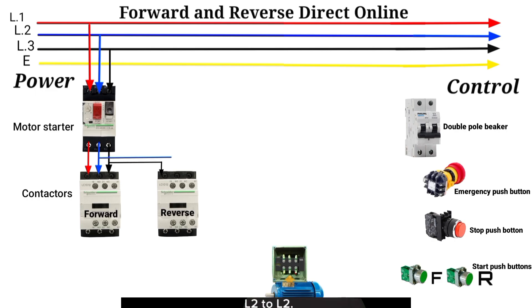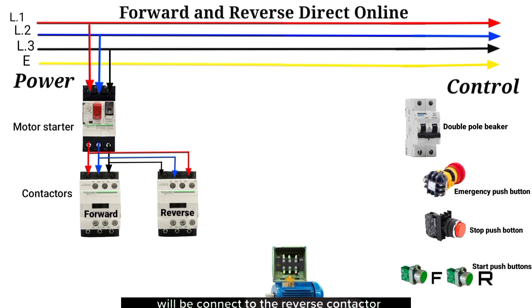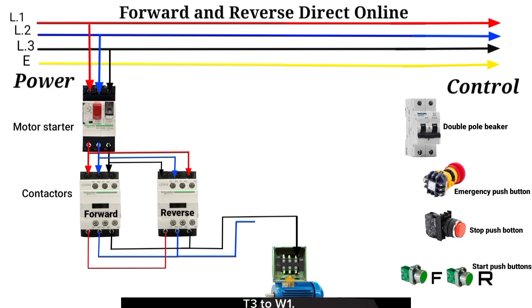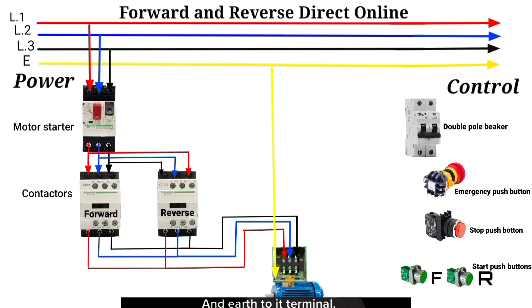The forward contactor input is looped to the reverse contactor input with a phase swap: L3 to L1, L2 to L2, and L1 to L3. The output of the forward contactor connects to the reverse contactor output: T3 to T3, T2 to T2, and T1 to T1. Reverse contactor output connects to the motor terminals: T3 to W1, T2 to V1, T1 to U1, and Earth to its terminal.